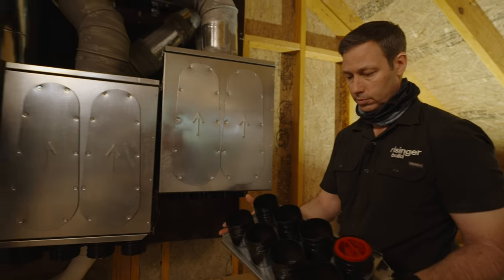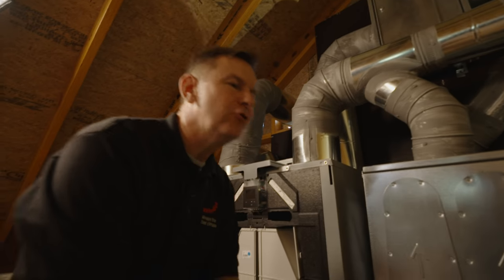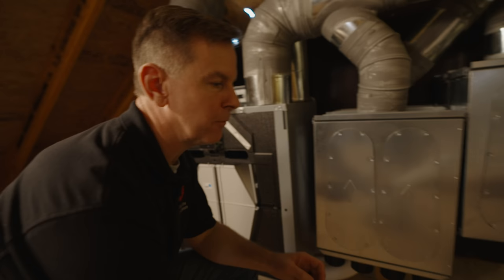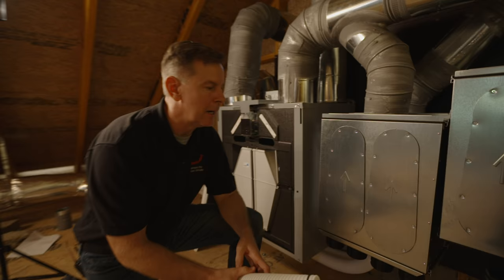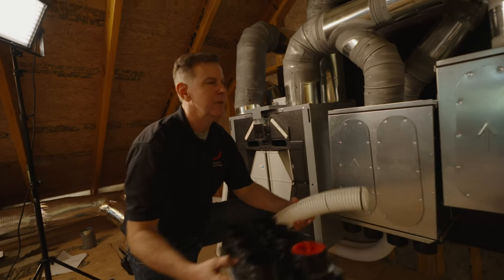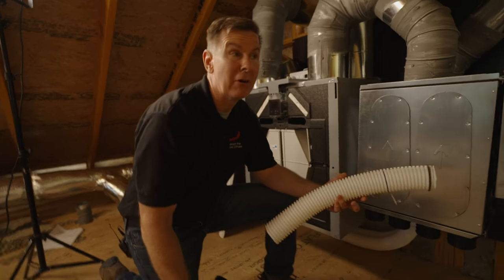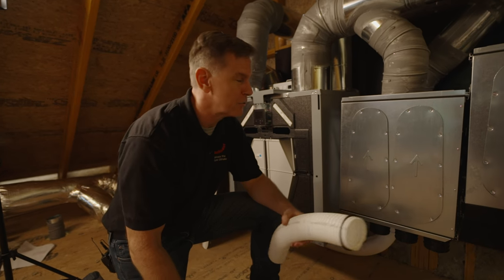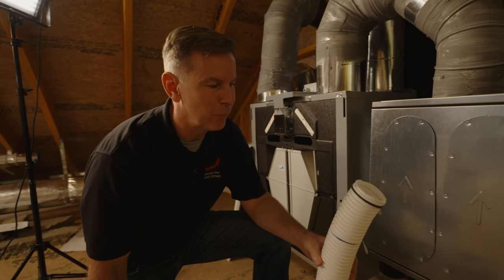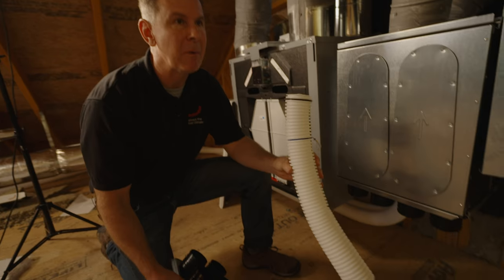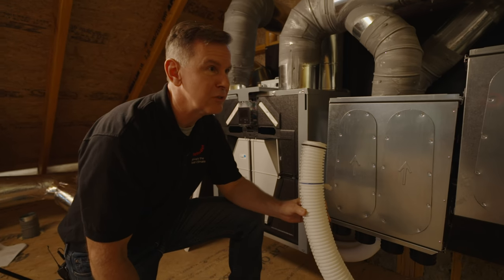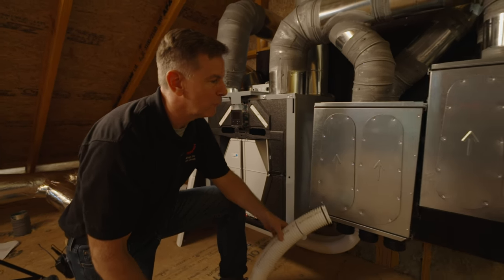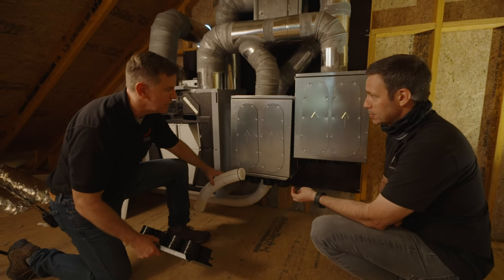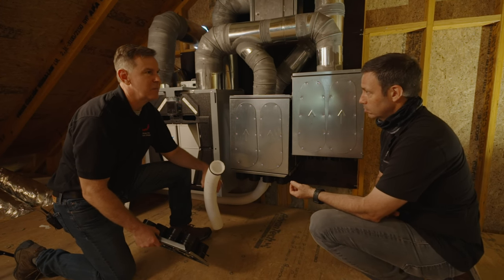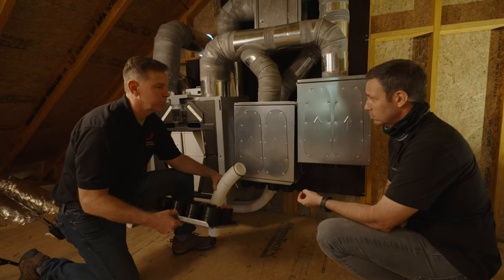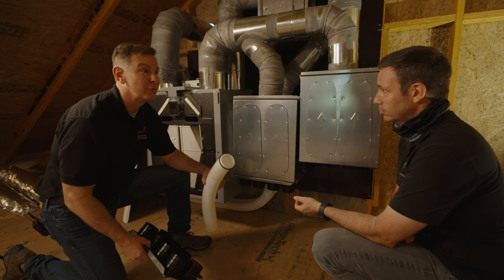What we want to do is give people an engineered solution, so when they go to connect the system up, they don't have to engineer a trunk and branch system and figure out how much flow is going to be in what branch. What we've got is this manifold system - we can plan for the same amount of airflow to go through each one of these tubes. We connect it to a manifold and give every tube on that manifold the same air pressure. That way we just plan in multiples, in our case, of 12 CFM per tube.